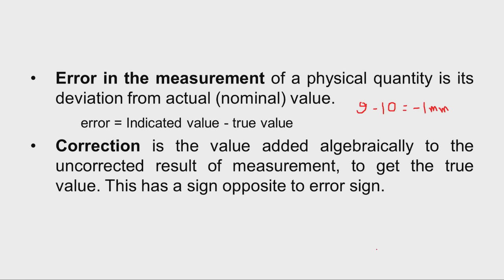Correction is the value added algebraically to the uncorrected result of measurement to get the true value, and it has a sign opposite to the error sign. For example, the uncorrected indicated value is 9 millimeters; the error is minus 1 millimeter, so we need to add plus 1 millimeter to get 10 millimeters. The correction factor of plus 1 millimeter has a sign opposite to the error sign of minus 1 millimeter.